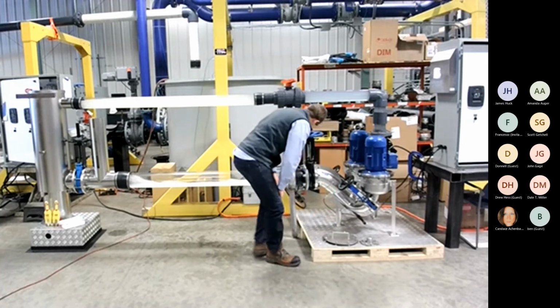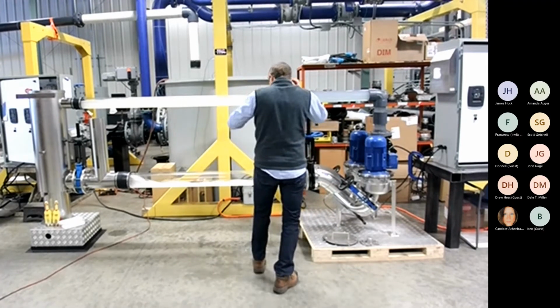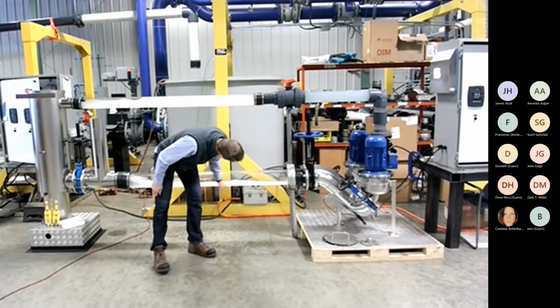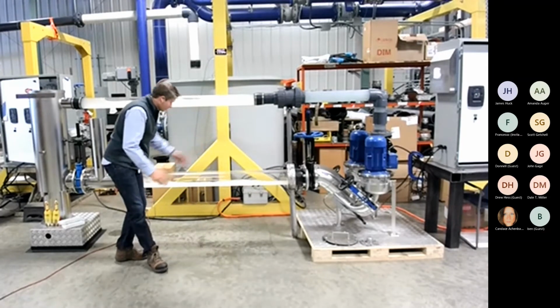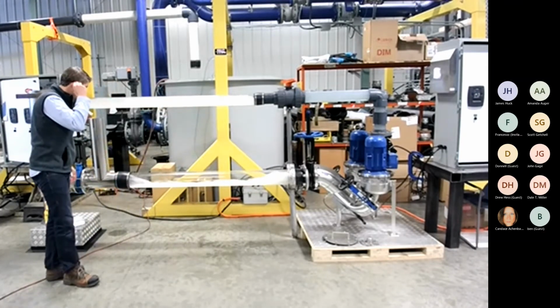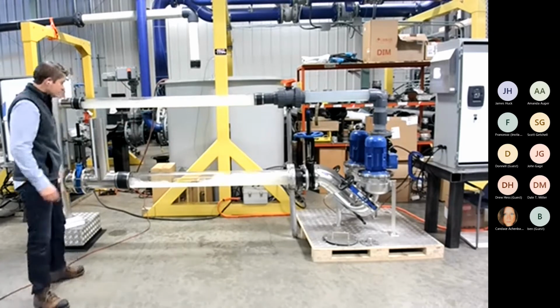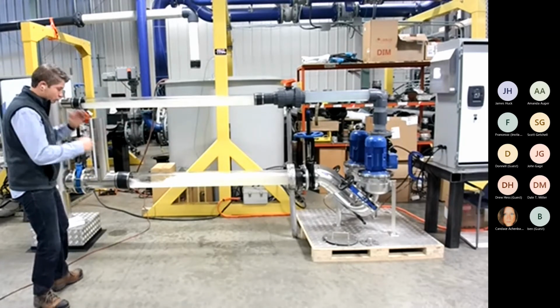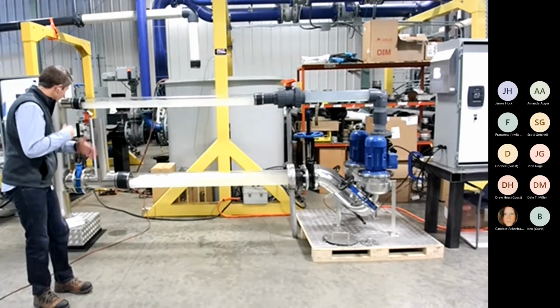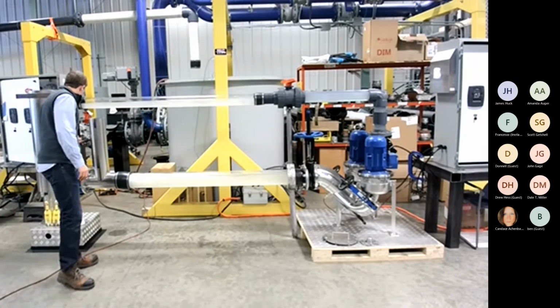So while I was talking, it filled back up and started running again. You can see I have a very, very low flow here. It's not even a quarter of the pipe. It did just turn off there. Again, it wasn't able to regulate it. It's running that algorithm to see if it's able to understand the flow rate that's coming in here.